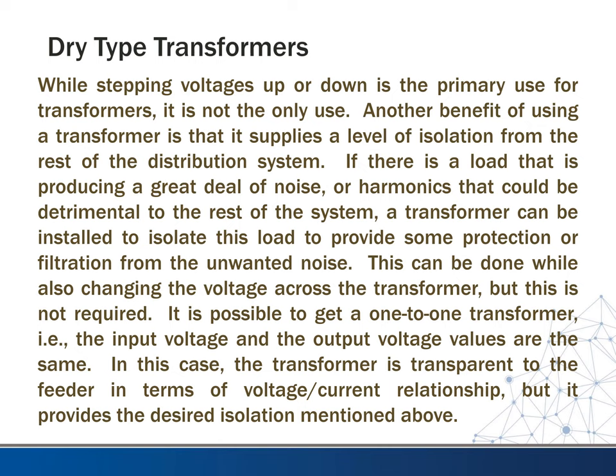While stepping voltages up or down is the primary use for transformers, it's not the only use. Another benefit of using a transformer is that it supplies a level of isolation from the rest of the distribution system. If there is a load that is producing a great deal of noise or harmonics that could be detrimental to the rest of the system, a transformer can be installed to isolate this load to provide some protection or filtration from the unwanted noise. This can be done while also changing the voltage across the transformer, but this is not required.